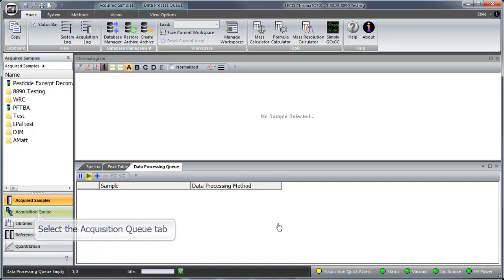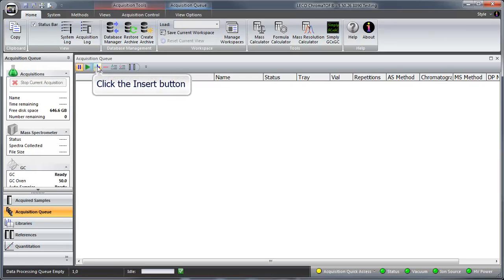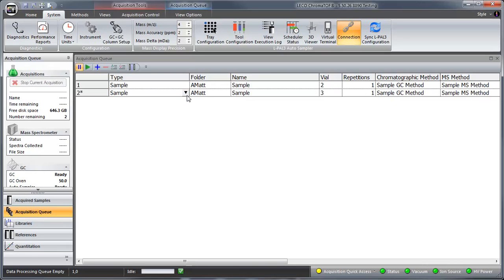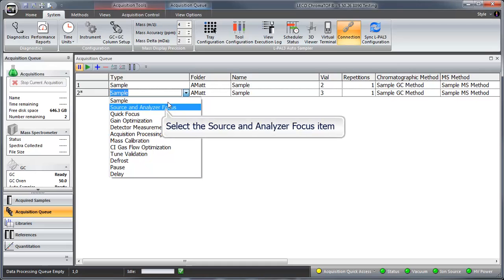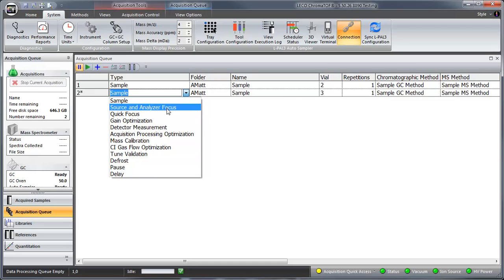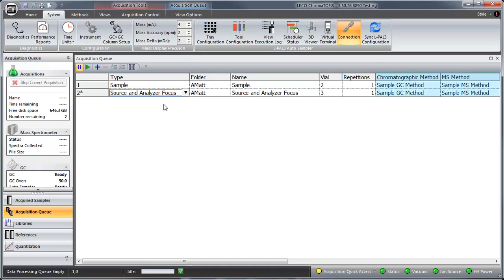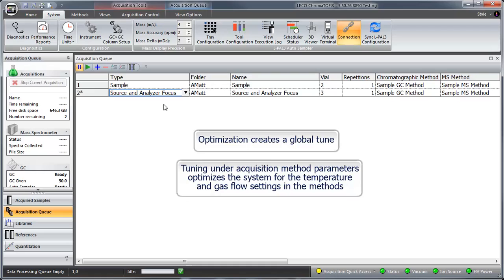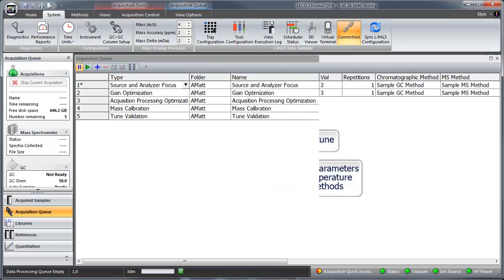To run a system optimization, select the Acquisition Queue tab and begin building an acquisition batch. Each optimization step can be added by creating a line item and manually selecting an option in the Type drop-down menu. Be sure to add a GC and MS method to each step of the queue. The optimization sequence will create a global tune, so it is important to select the GC and MS methods that will be used for sample collection in order to allow the system to account for any changes caused by gas flow and temperature settings in the methods.